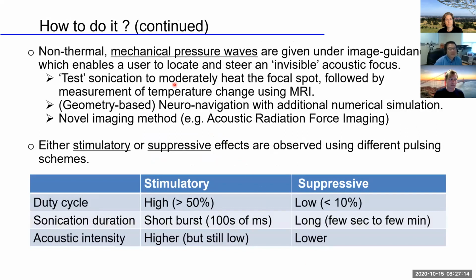Here is the continuation from the previous page regarding the technique in a nutshell. First, non-thermal mechanical pressure waves are given under the image guidance, which enables operator to locate and steer the invisible acoustic focus. For example, test sonication is applied to moderately heat the focal spot, while on-site MRI is used to measure the temperature change. If you want to avoid hitting the brain tissue, neuronavigation with additional numerical simulation can be employed to estimate the geometric location of the focus. We are currently using this approach.